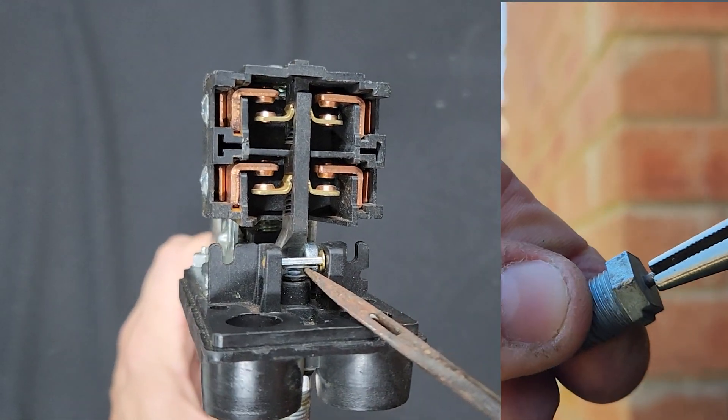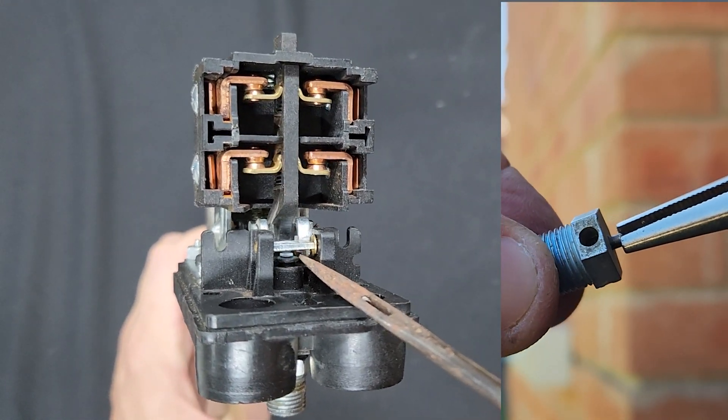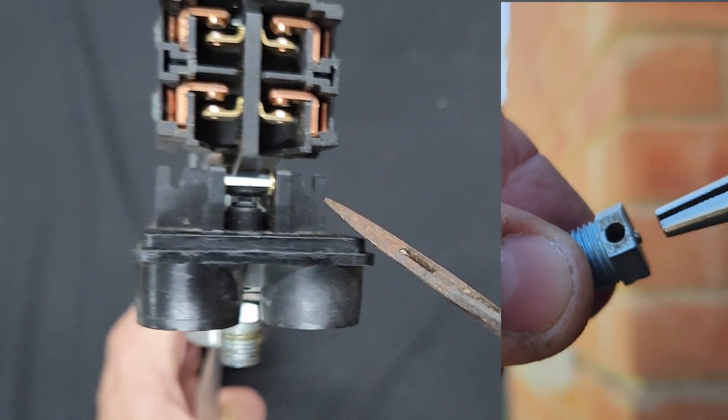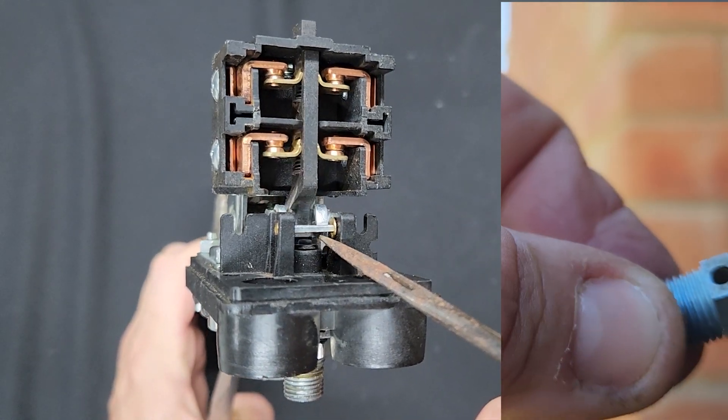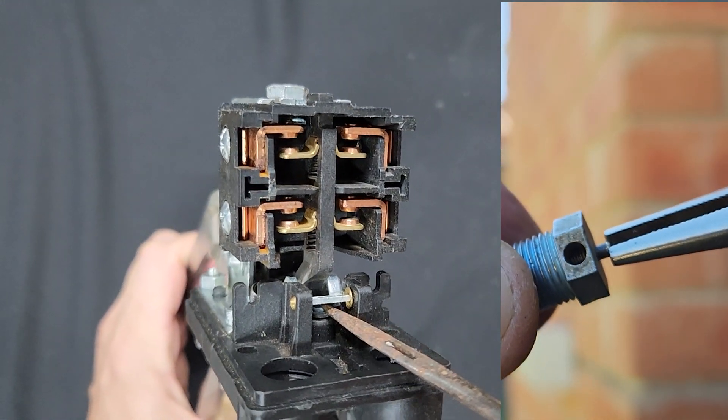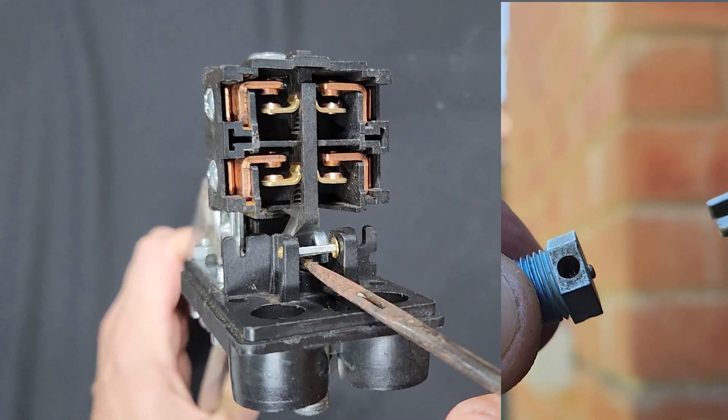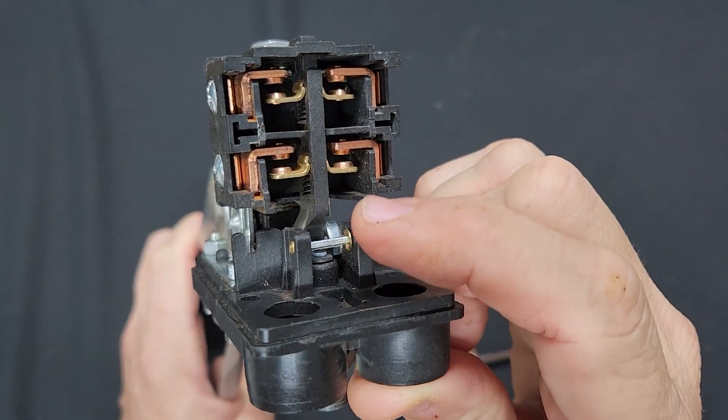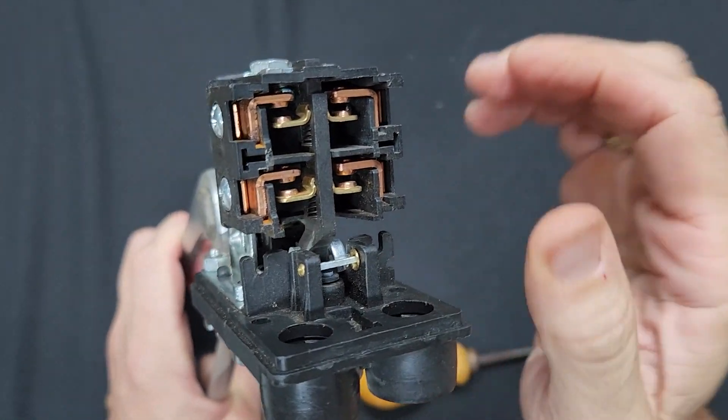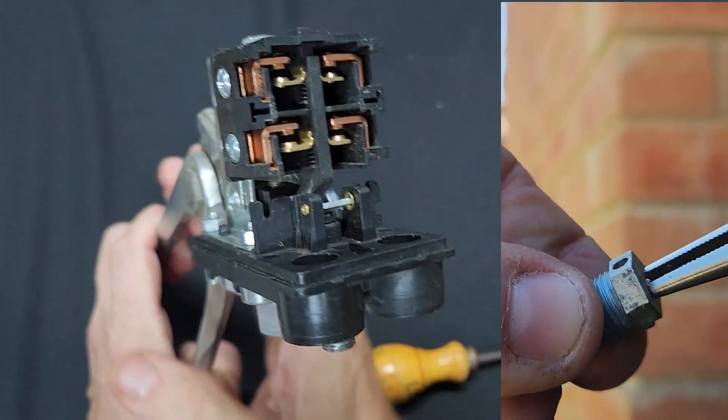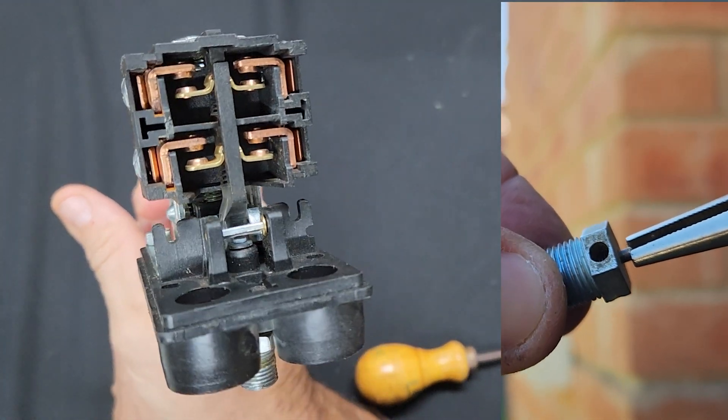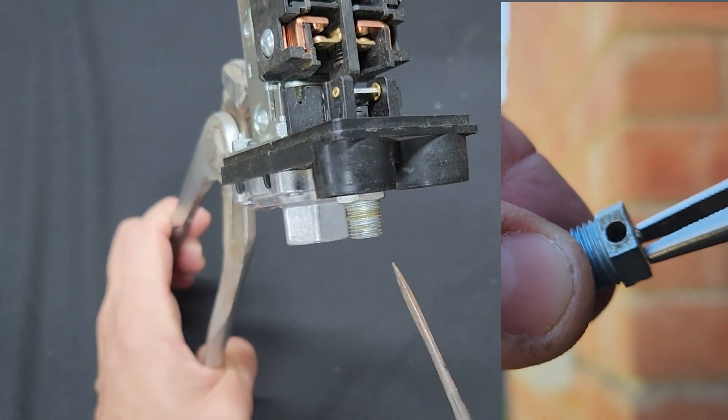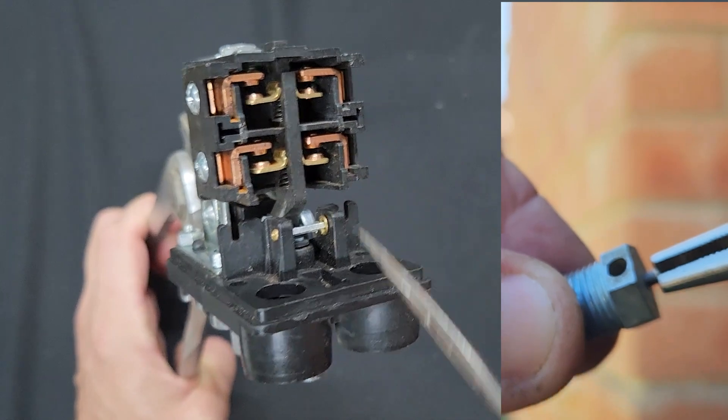Then once this gets actuated, have a look at this part here. Did you see that? That part right there presses down. So when the compressor switches off, that pushes down. What's it pushing down on? It's pushing down upon the needle of the unloader valve. Well what does that do? Well if you remember, when the unloader valve is pressed down it's open, and so when this is off, that last bit of air that's left in the pumping line gets expelled out this exhaust line.